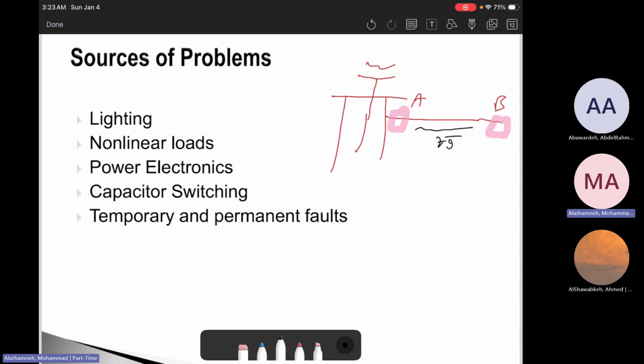The other thing, also in Jordan, is capacitor banks in medium voltage feeders. In Jordanian utilities, we have capacitor banks on medium voltage levels to improve the voltage, make power factor correction, reduce the losses, and supply reactive power. Those are very good, but they have a side effect: transient overvoltage occurs, an oscillatory transient appears, and sensitive equipment may trip. If the capacitor switching is not synchronized or properly damped, PLCs will trip, VFDs (variable frequency drives) trip, electronics malfunction, computers can be reset, and routers can be reset as well.